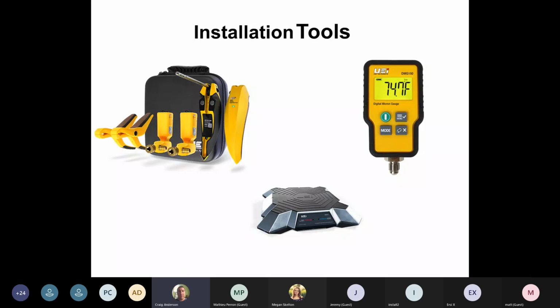This little setup up in the corner, this is called a Hub 6. This is made by UEI. If you're looking to buy yourself a little Christmas gift or a birthday gift, and you do a lot of service on air conditioners, this is a cat's meow. It has 2 clamp-on meters to go on your liquid and suction pipes outside. The center is your gauges. You're not dealing with the round gauges that are bouncing around, and the hoses. This is just screwing on to your high and low side.